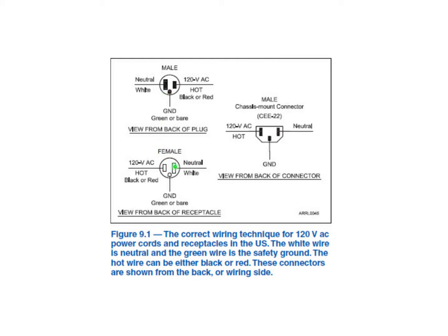here, or on the right, if you're viewing it from the back of the receptacle, this is the neutral. And then the other one is the hot wire coming in. And then the ground goes back to the ground rod that's probably outside of your house, as close as they could get it to your electrical panel.